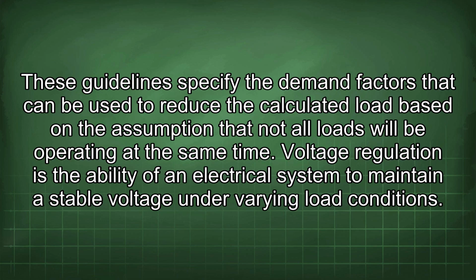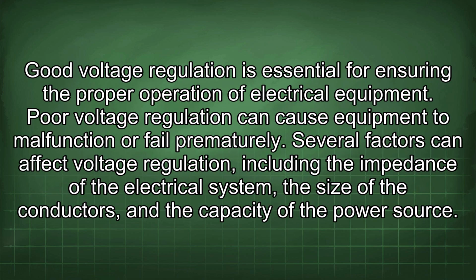Voltage regulation is the ability of an electrical system to maintain a stable voltage under varying load conditions. Good voltage regulation is essential for ensuring the proper operation of electrical equipment. Poor voltage regulation can cause equipment to malfunction or fail prematurely. Several factors can affect voltage regulation, including the impedance of the electrical system, the size of the conductors, and the capacity of the power source.